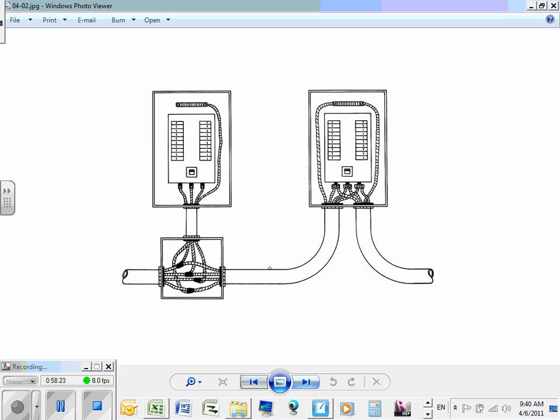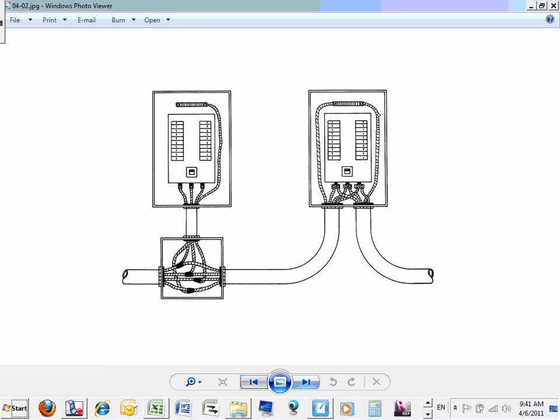So if I can draw, imagine this cable, guys, is a 225 amp panel, 225 amp cable. You come over here to a 225 amp circuit breaker. From the line side, you'll have 2 lugs here. You have to have 2 lugs, 1 lug in, 1 lug out, in and out for each phase, and a neutral. Can you see the neutral here? And then you tap from the line side, go feed another panel, and a 3rd panel, and a 4th panel.